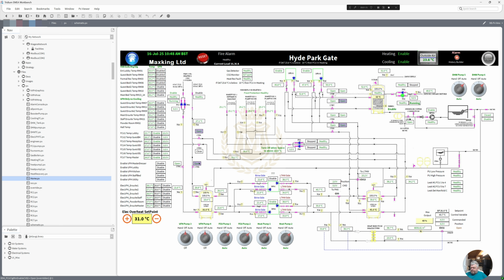The reason these are purple is the mechanical engineer asked for these to be open, just one valve. They fitted two valves per circuit, but they didn't need to, so the mechanical engineer asked for each one of these sets of valves to be open all the time, so hence that's why they're overridden. So we've got CV1 and CV2 open, and we're pulling out.